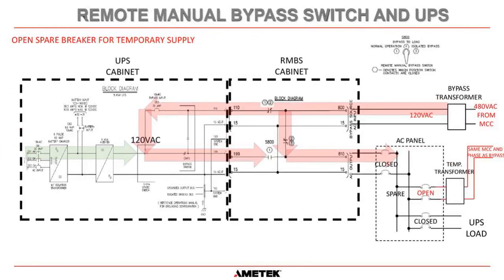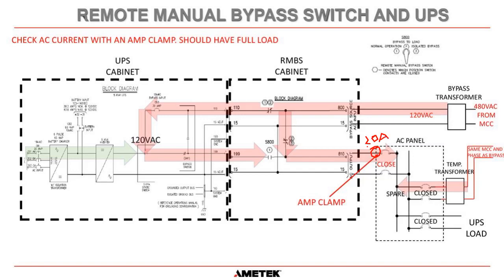And then once we've checked that there is current, we can open that breaker with confidence because we now know that this is going to feed your critical loads. The last thing we do is take the amp clamp. What should we have at that position here? We should now have the full load current of 20 amps. Just double checking absolutely everything to make sure we are doing things correctly. Okay. So now we are pretty much back to normal. Our backfeed breaker, that should say, is open. I missed that one. This one here should say closed.